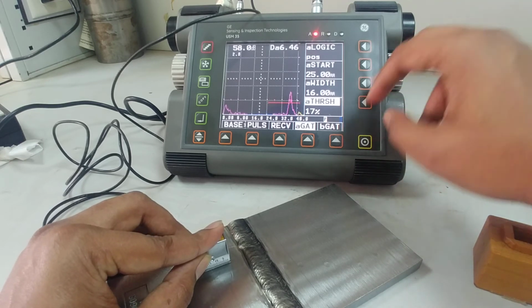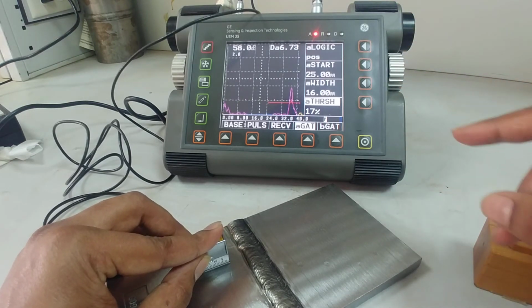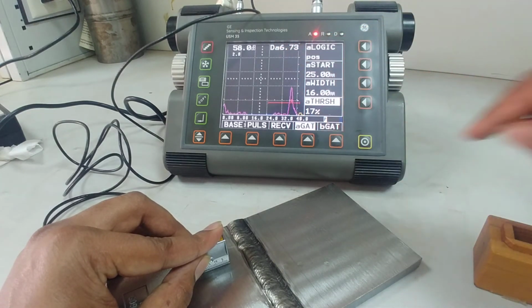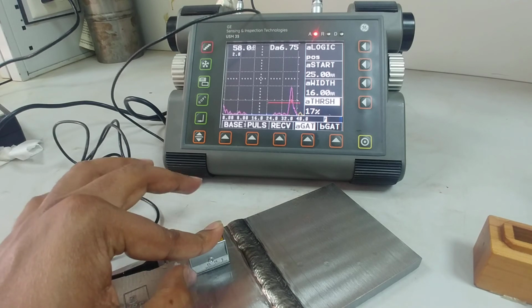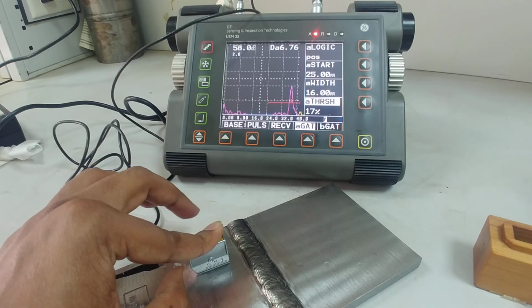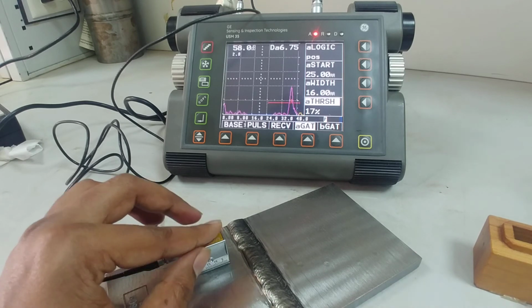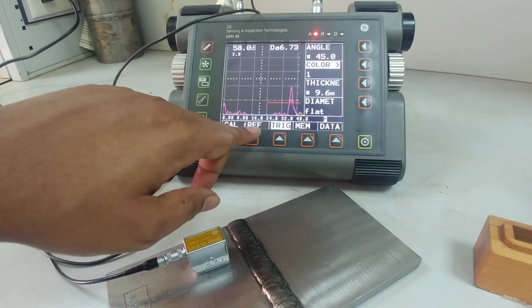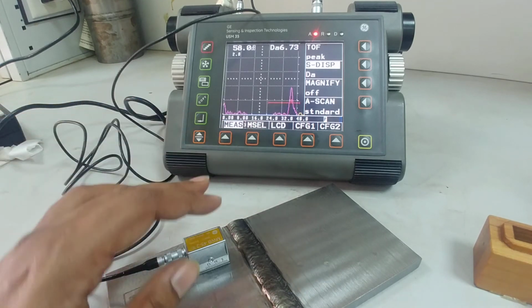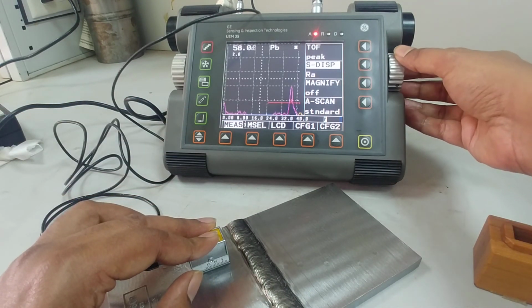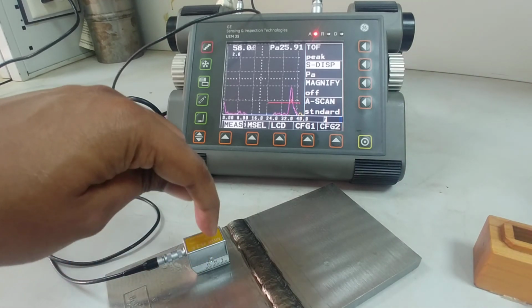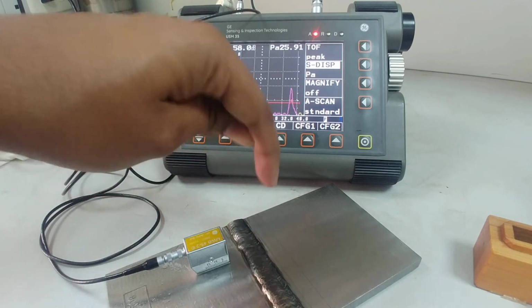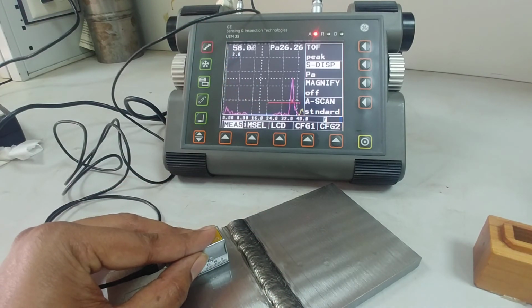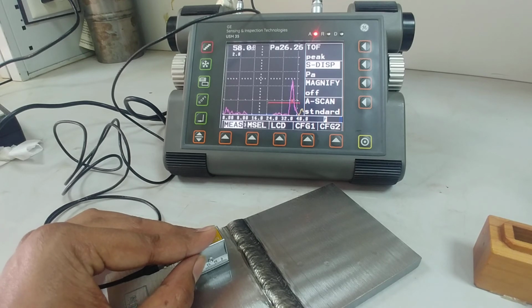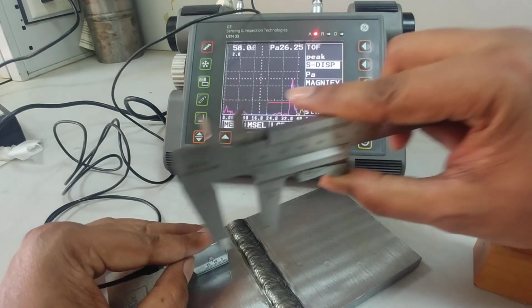So I got some defect over here. It's directly giving me the depth value at which the defect is. I'm having this defect at a depth of 6.75 because I have already set the values, so it will straight away give me those values. Now if I want to see other things, like the projected distance from this index point to where the defect is, if I set it, we can see it's showing 26.25. At 26.25 distance from the center point, I'm having this kind of defect.